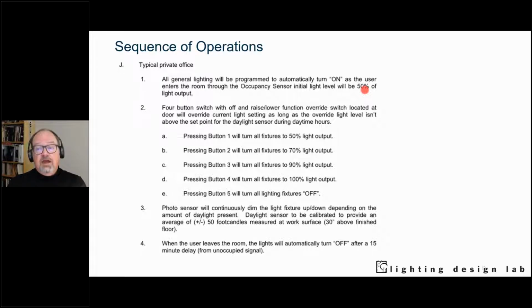So you have the ability—in this case pressing button 1 is 50% light output, but you can press 2, 3, 4 to get all the way up to 100% light output in cases where you need that. The reality is most people leave it at 50%, so that reflects the savings there. This also gives us information about the photo sensor, daylight sensor calibration, and the timeout—basically everything somebody would need to program a typical private office in this project is listed in this sequence of operations.